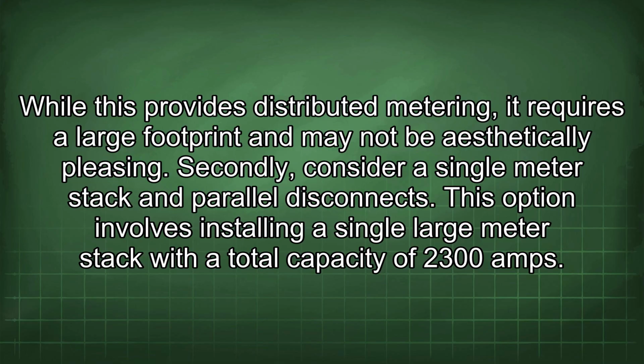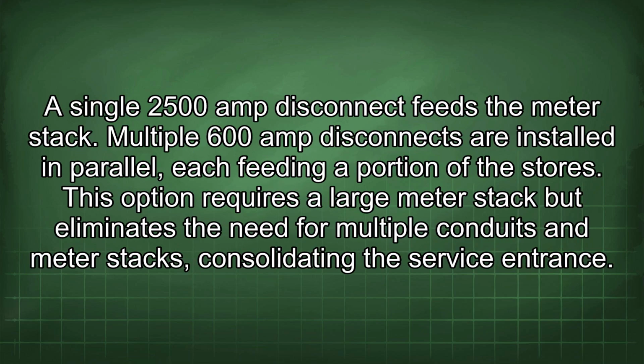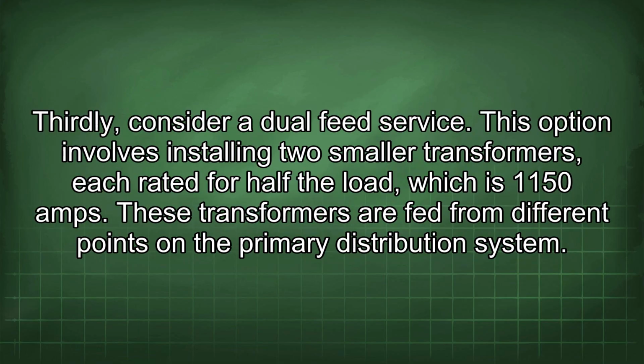Secondly, consider a single meter stack and parallel disconnects. This option involves installing a single large meter stack with a total capacity of 2300 amps. A single 2500 amp disconnect feeds the meter stack. Multiple 600 amp disconnects are installed in parallel, each feeding a portion of the stores. This option requires a large meter stack but eliminates the need for multiple conduits and meter stacks, consolidating the service entrance. Thirdly, consider dual feed service.